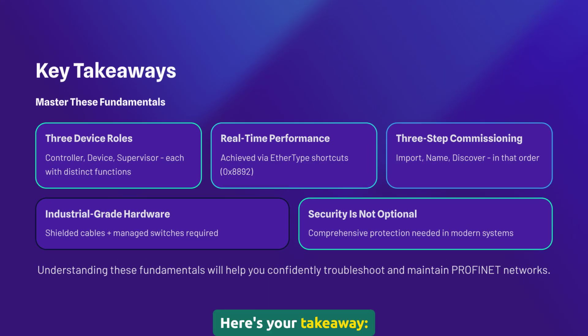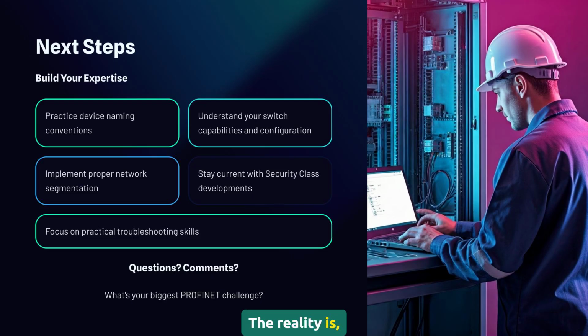Here's your takeaway. PROFINET isn't magic, it's just smart engineering. It takes standard Ethernet and adds the intelligence needed for real-time control. Master those 3 device roles, understand the real-time shortcuts, follow the 3-step commissioning process, avoid those common cable and naming mistakes, and never ignore security. The reality is, once you understand these fundamentals, PROFINET becomes one of the most reliable and flexible networking technologies you can deploy.